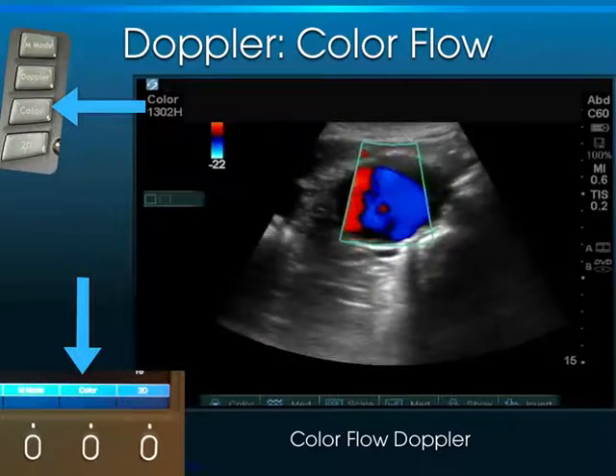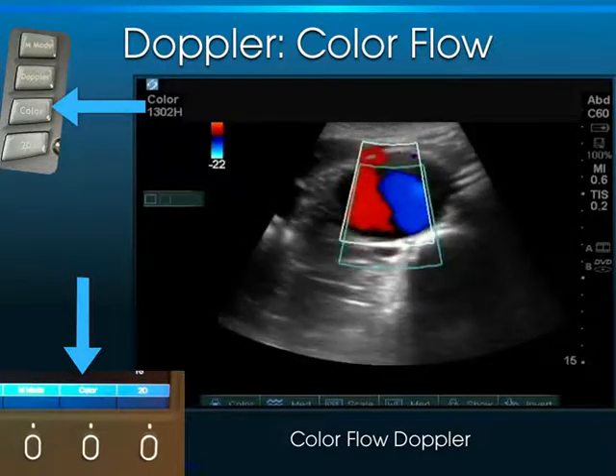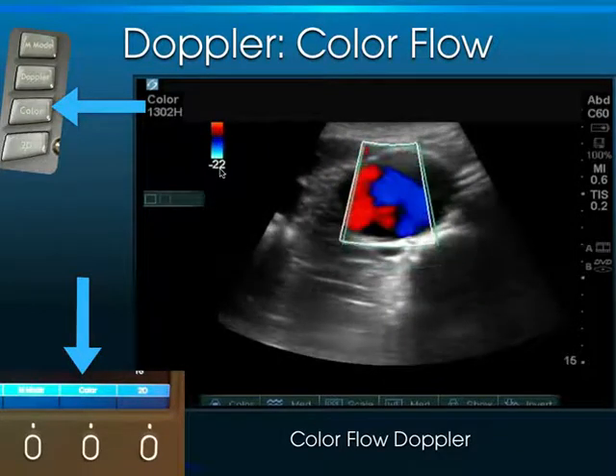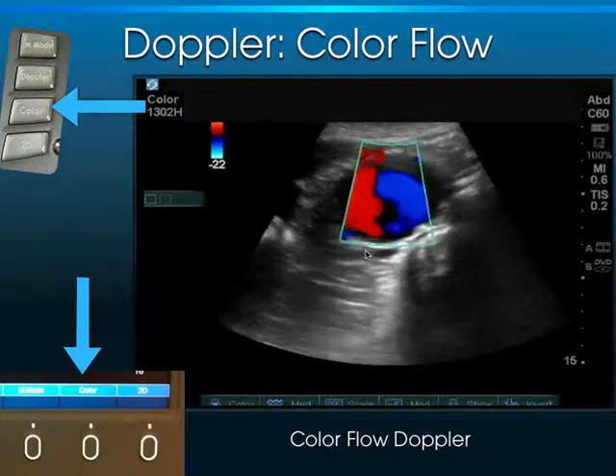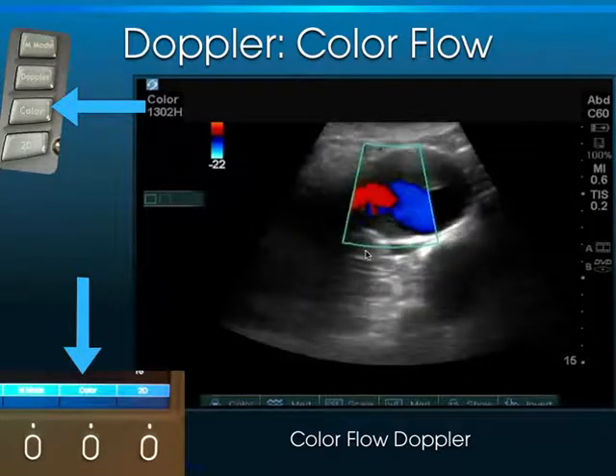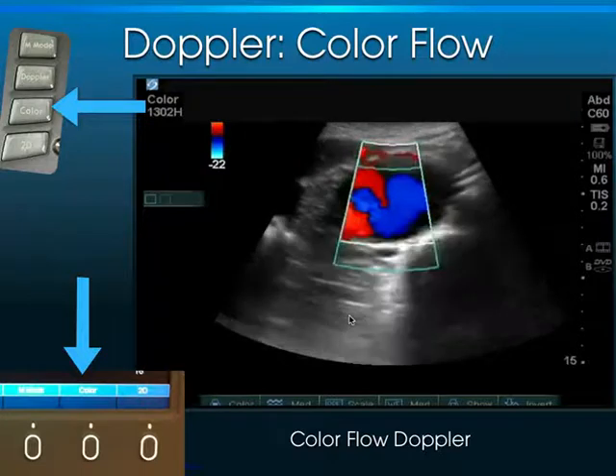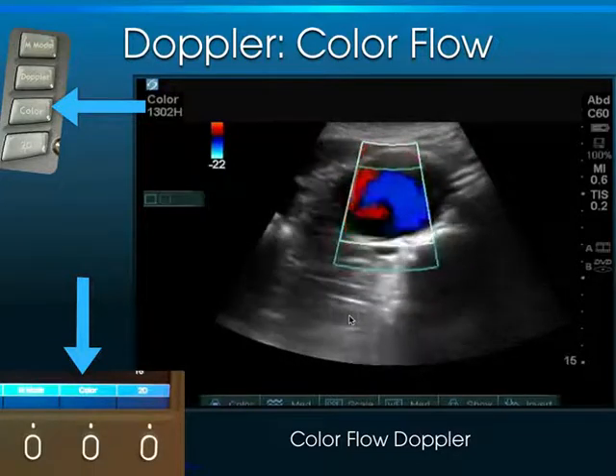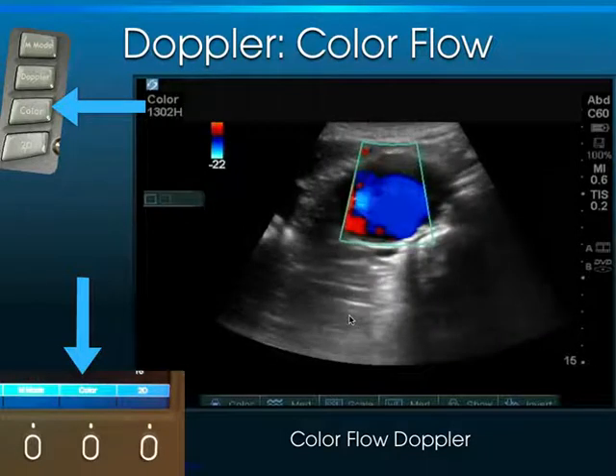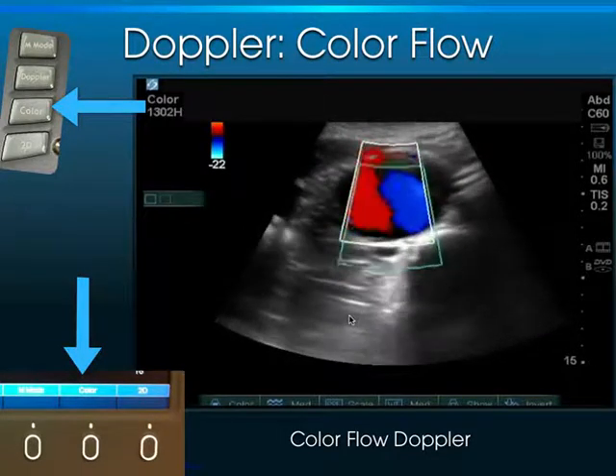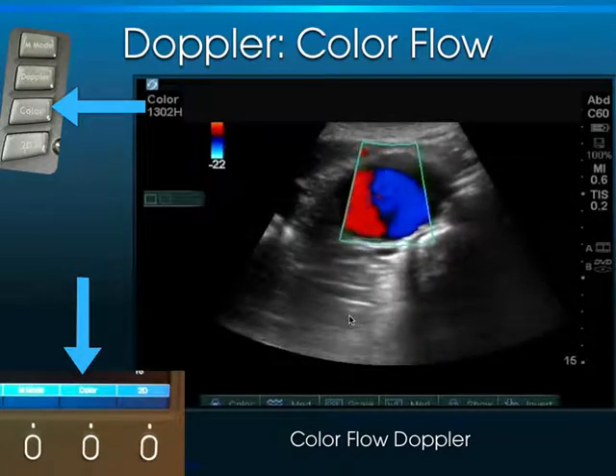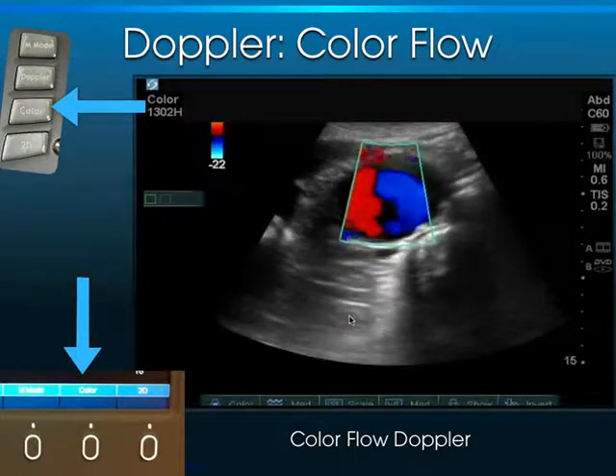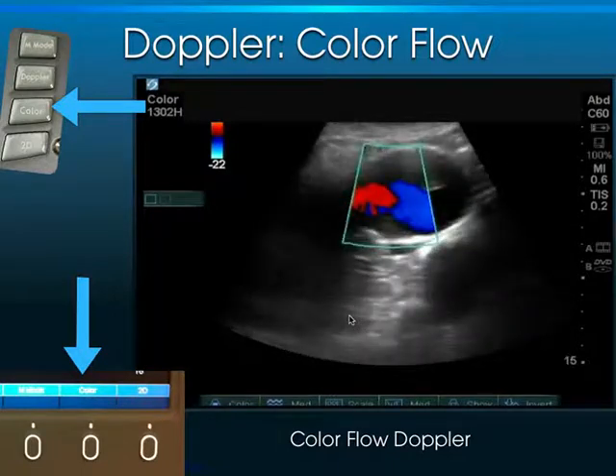The other mode is Doppler, and there are different types. Color flow Doppler: red is flow towards the transducer, blue is flow away from the transducer. Angle the probe to anticipate flow direction — it should be red or blue and make sense. At 90 degrees, the cosine of theta is in the numerator of the Doppler equation. Since cosine of 90 is zero, you won't get any flow information, so you need to angle off 90 degrees.